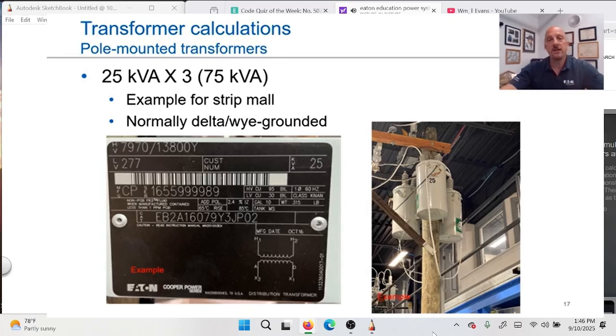But in this case, if you don't know the impedance of a pole mounted transformer and you guess that high, guess what you're going to do? You're going to influence your fault current calculation. So it's important that you don't overestimate the impedance of a pole top transformer. And so if I don't know the value, I might even guess 2% for that one. So 2 to 3% is a typical number.